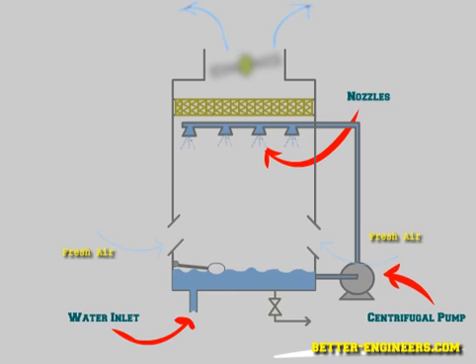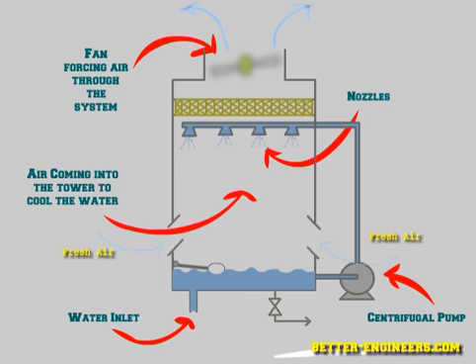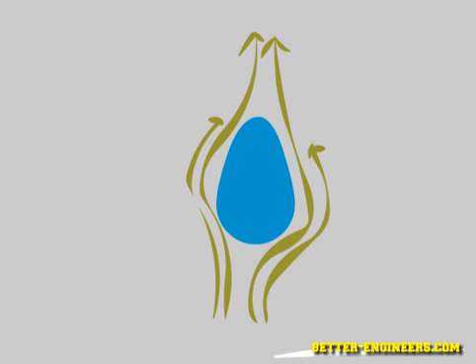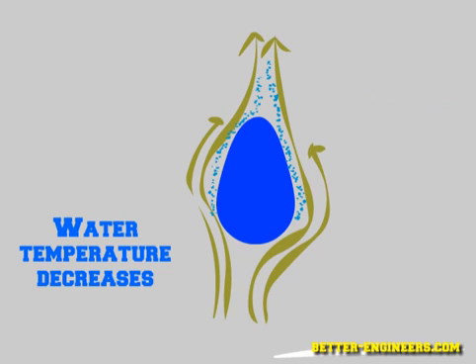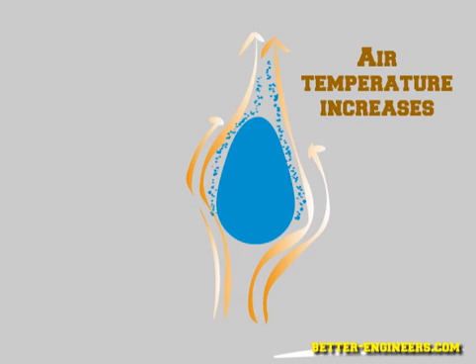At the same time, a fan, in this case located at the top of the tower, moves fresh air which comes into contact with the hot water. During this contact, part of the water will evaporate. As this evaporation needs energy, the temperature of the water decreases and that of the air increases.